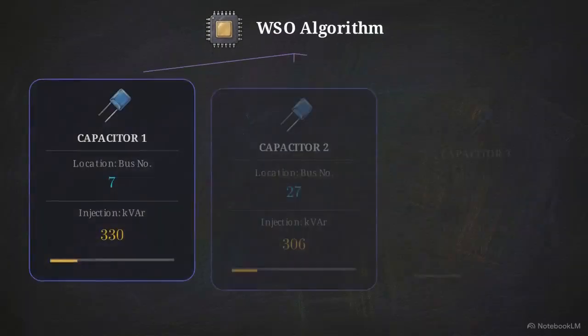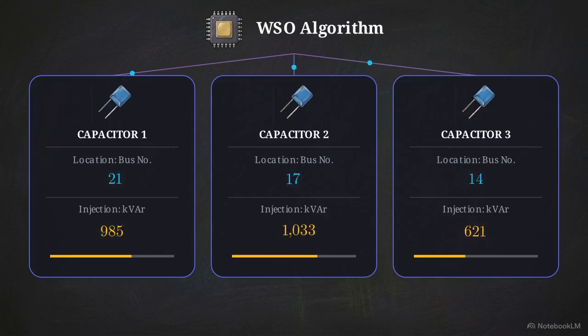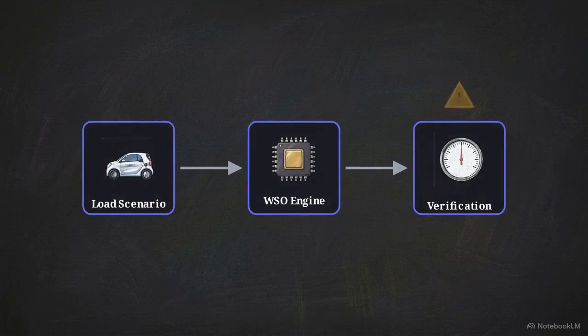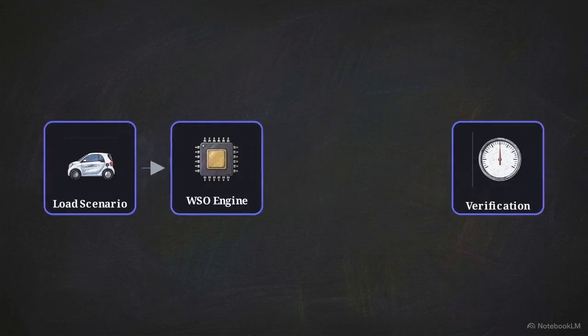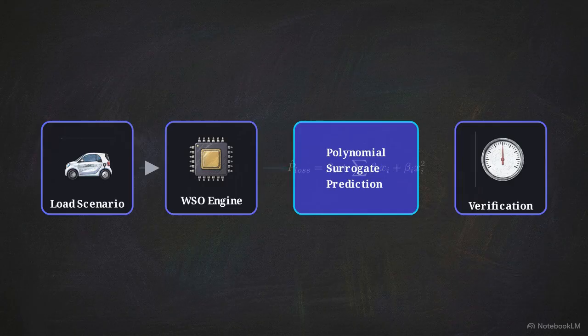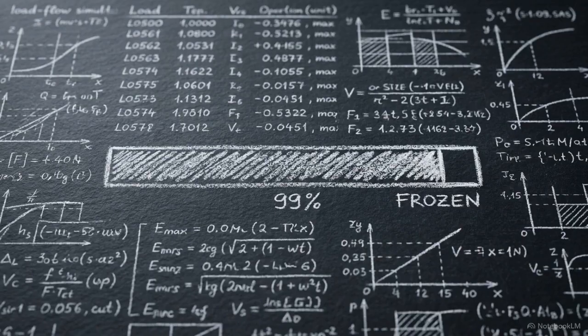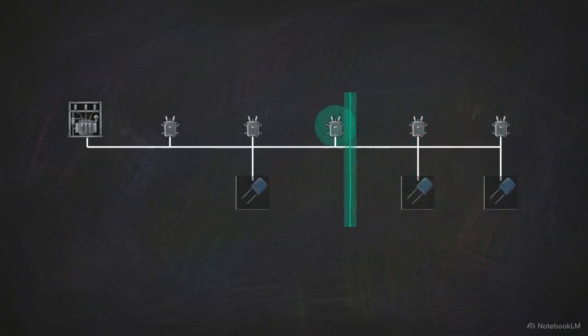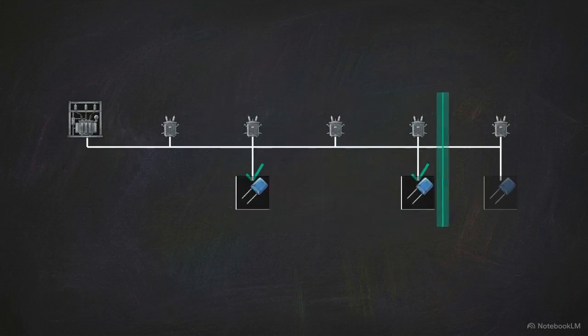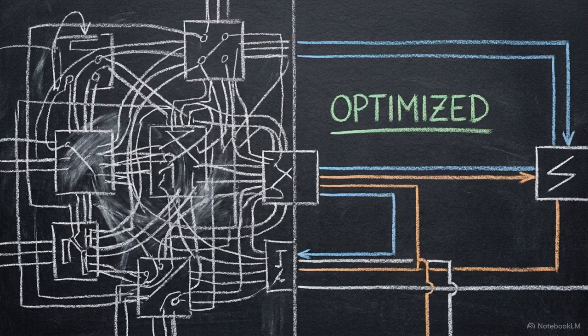The WSO algorithm continuously manipulates 6 specific variables: the physical bus locations for the 3 capacitors, and the precise kVAR injections assigned to each. To prevent computational bottlenecks, the framework embeds an efficiency engine inside the WSO, a ridge-regularized polynomial surrogate model. Rather than running a full equation every time, the surrogate acts as a local predictor. It evaluates promising configurations on the fly, drastically reducing the number of heavy load flow evaluations needed to find a valid solution. But the model doesn't replace the physics. Once the surrogate identifies the best candidates, the final solutions are rigorously verified using a stable backward-forward sweep load flow. This hybrid approach gives utilities the mathematical leverage to map the steep, nonlinear power losses of heavy EV loading without computational burnout. Let's look at the first test.